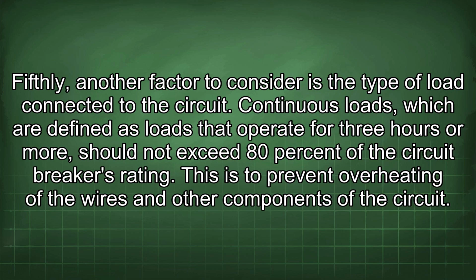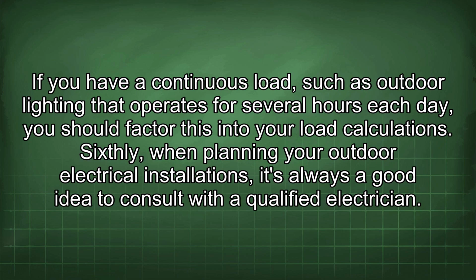Fifthly, another factor to consider is the type of load connected to the circuit. Continuous loads, which are defined as loads that operate for 3 hours or more, should not exceed 80% of the circuit breaker's rating. This is to prevent overheating of the wires and other components of the circuit. If you have a continuous load, such as outdoor lighting that operates for several hours each day, you should factor this into your load calculations.